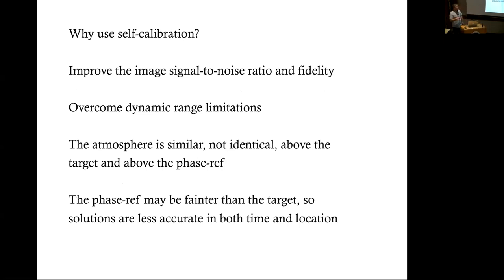The atmosphere is going to be similar over your calibrator and, hopefully, similar over your target, but it's not the same, and they're not observed at exactly the same time—unless you're going to be looking at a calibrator as your target. So doing self-calibration effectively makes that change for you: it says, well, we are going to use your source as a calibrator and calculate the gains.